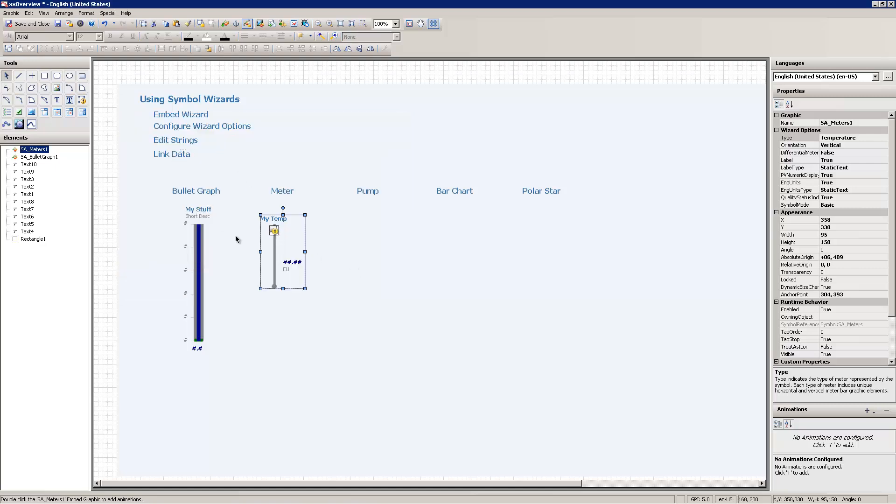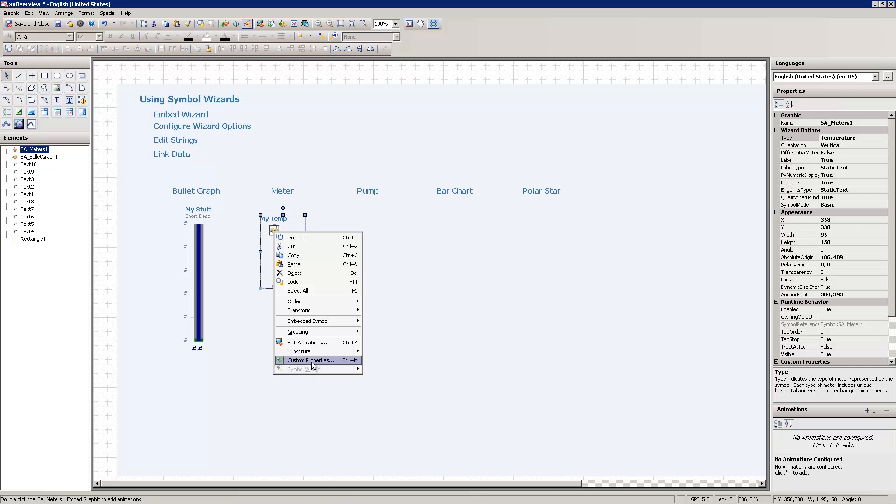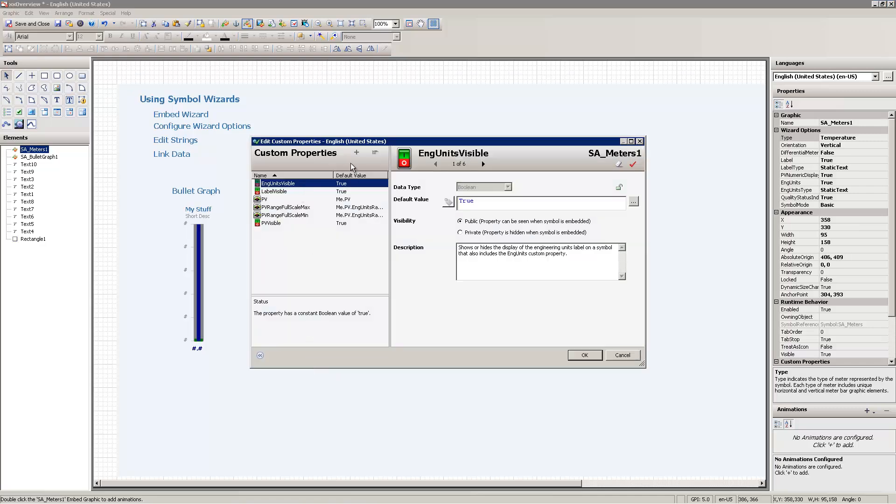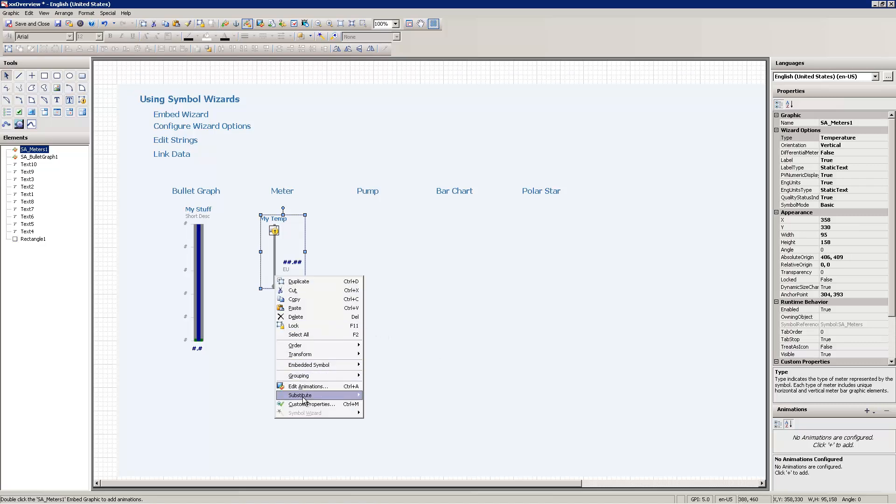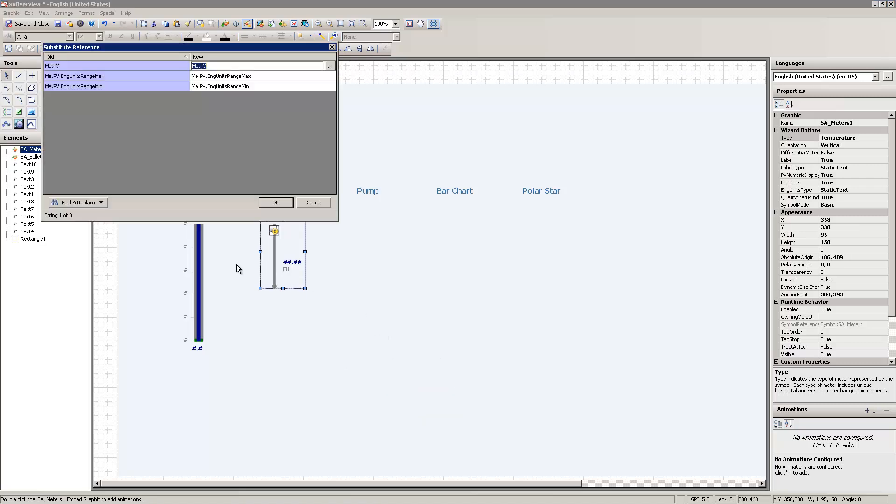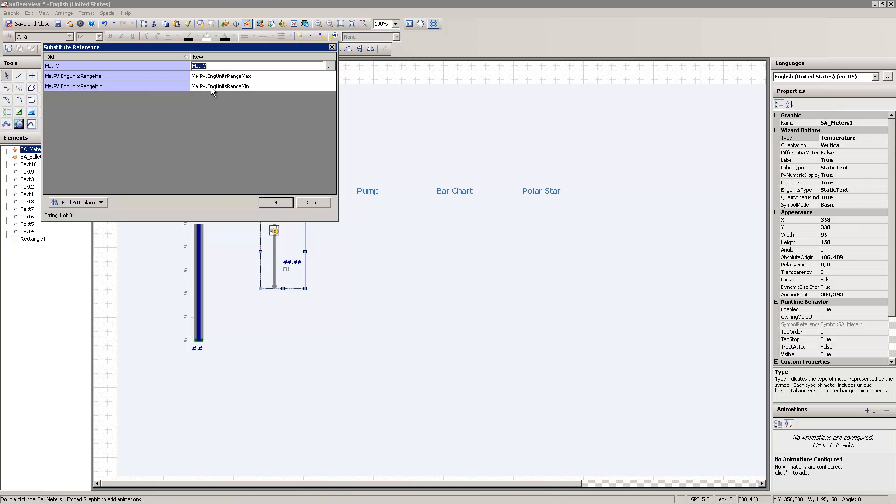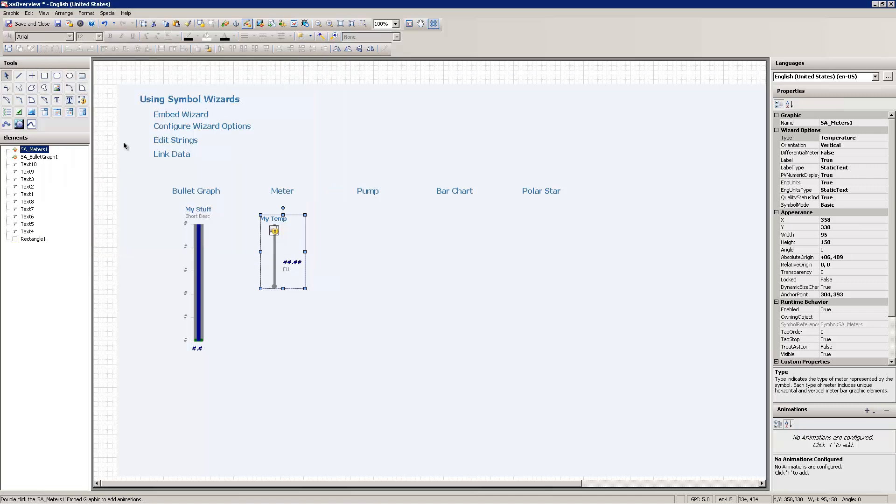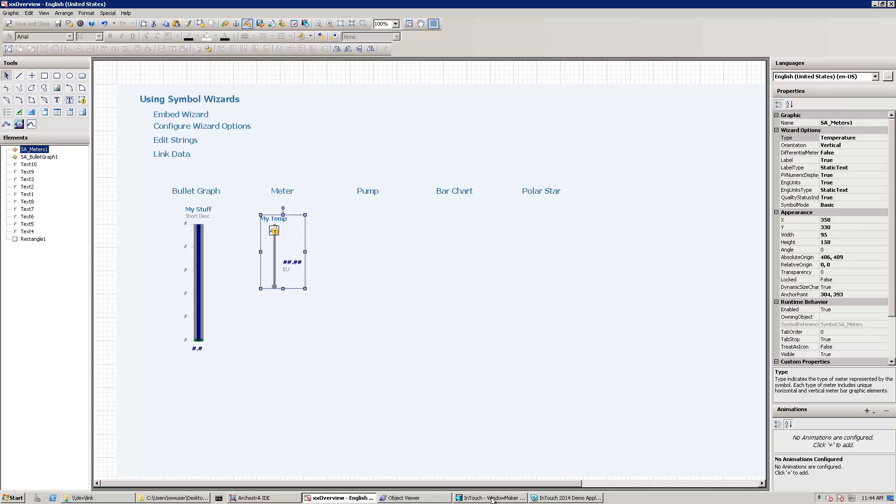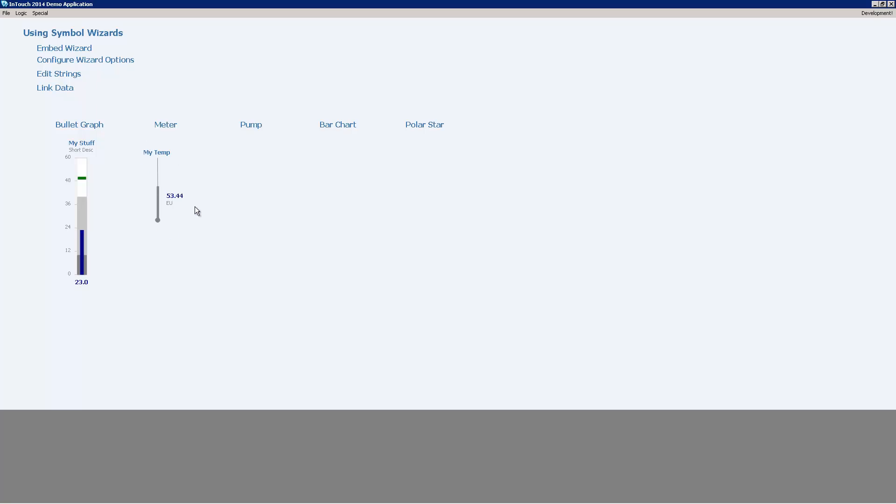Now I need to link the data. To link data, I can do it in actually multiple ways. One of the first ways I can do is I can come in here and edit them individually through the custom properties. Or what I can do here is I'm going to hit cancel there, and I'm going to do substitute references. This will go through and look at all the references. This has some predefined references, which are all set around me dot, me dot pv, and the range max, and the range min. So what I'm going to do is I'm going to replace all the me's with a simulation object that I've got running called plc sim, and replace all of those and say OK. Now I'm going to save, swap back over to runtime, have a look, and my temperature meter is animating appropriately.